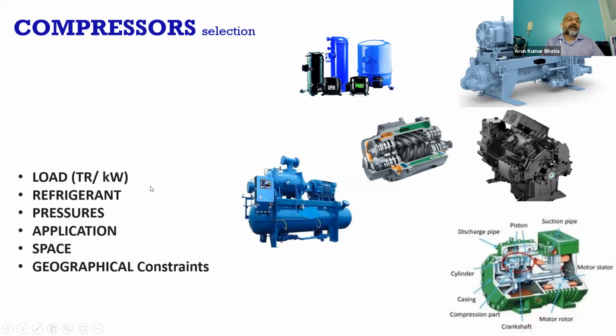Remember, refrigeration is all about pressures. Temperature is only a result of pressures. A compressor is nothing but a pressure generating machine, or a pump. It takes low temperature, low pressure refrigerant and pushes it to high temperature, high pressure refrigerant. Based on the application, the compressor selection is important.